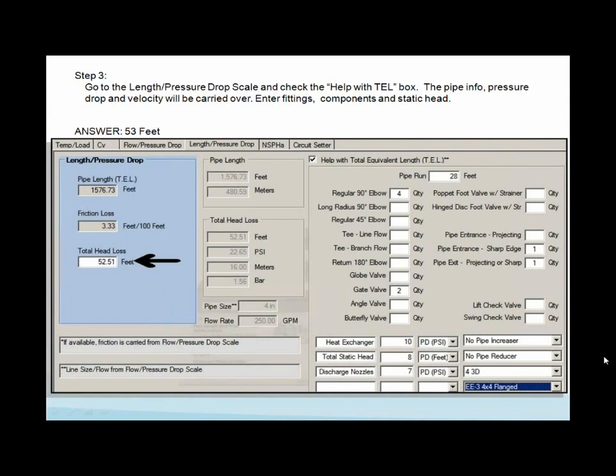Isn't that beautiful? Coming on the right-hand side, we had a 4-inch triple duty valve. We'll just plug it in. It already knows what the pressure drop is of the Bell & Gossett triple duty valve. It also has suction diffusers. We just picked the EE-3 suction diffuser. We plug it in. And now I think you begin to see we've got everything detailed out in that piping system for a total pump head calculation. We got every nut and bolt listed. Everything in that loop, that critical loop, has been listed.